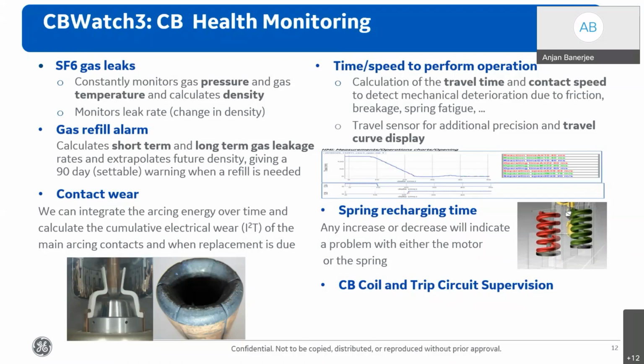so that the circuit breaker maintenance can be taken up in a disciplined way. Apart from that, the device also captures the interrupting current and the arcing time and computes arcing energy, which is nothing but the square of the interrupting current multiplied by the arcing time. By integrating this arcing energy, the device can estimate the cumulative electrical wear of the circuit breaker contact, and if the value exceeds the threshold, the device would generate an alarm. Another beautiful feature of this device is that it can compute the travel time and the speed of the circuit breaker contact.